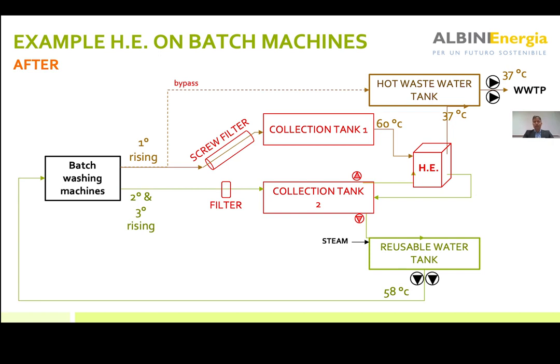So the basic idea was to reduce the temperature of this water system by increasing the temperature of the reusable water, in order to get two advantages: first, to avoid the cooling tower investment; second, to increase the temperature of the reusable water, reducing the consumption of steam which was previously used to reach the 58 degrees shown in the image.